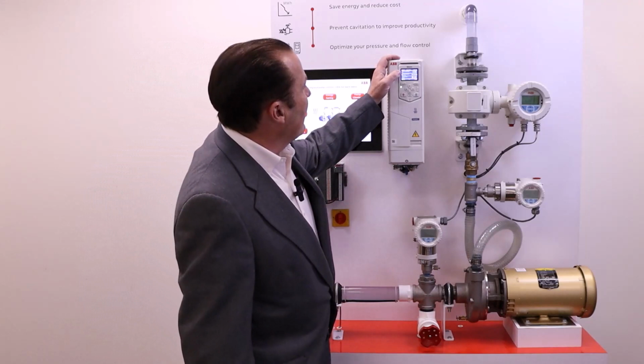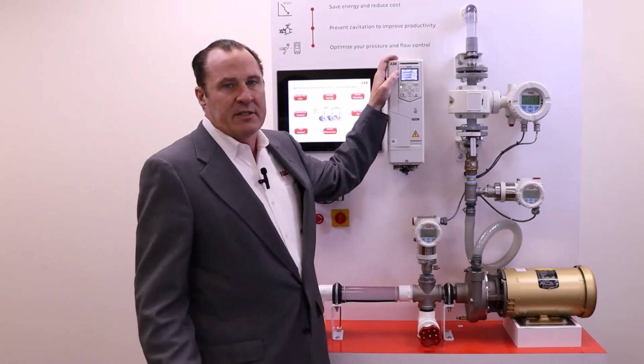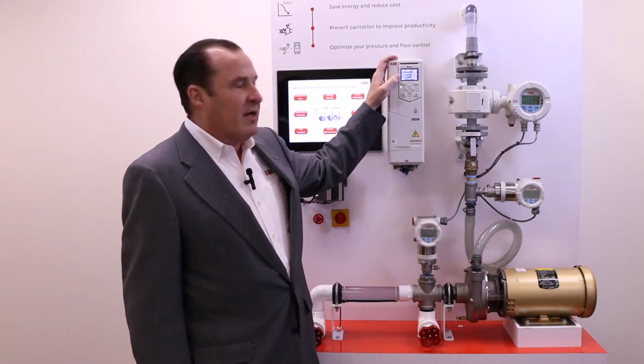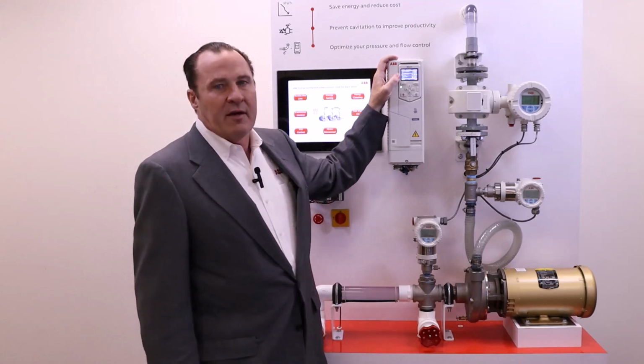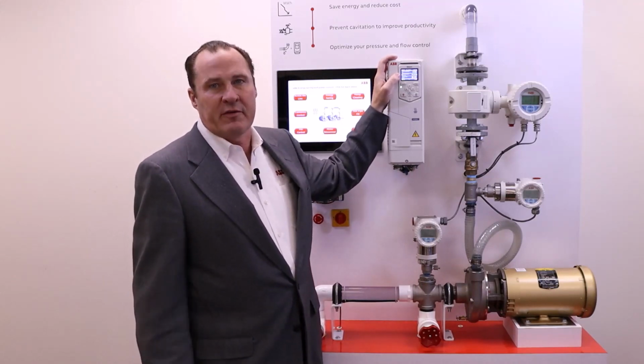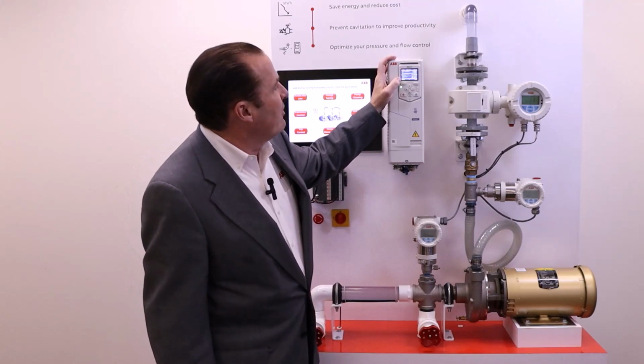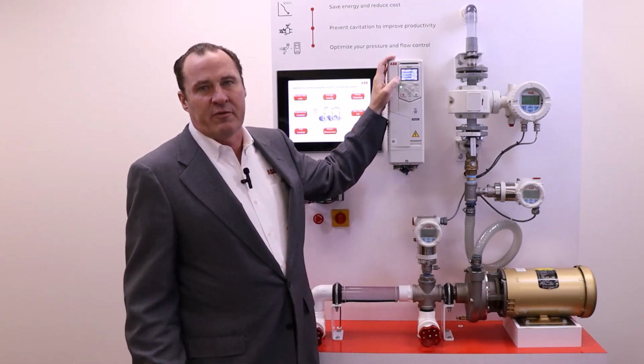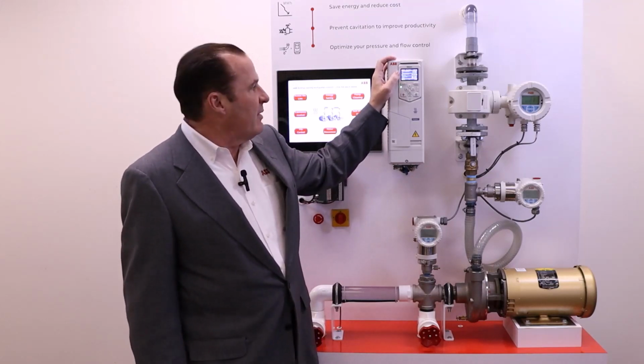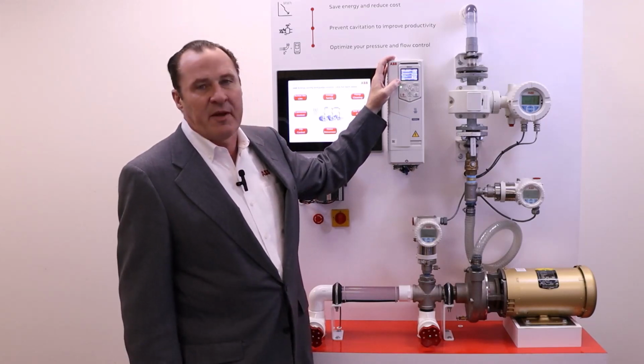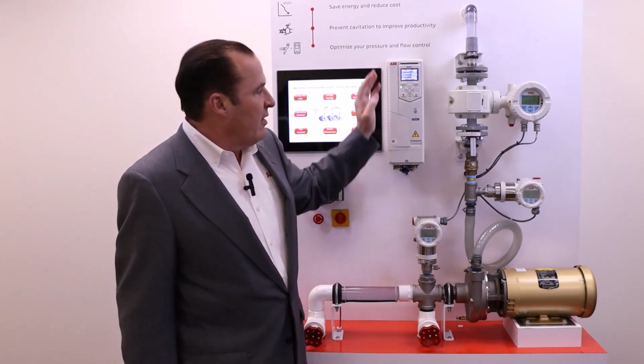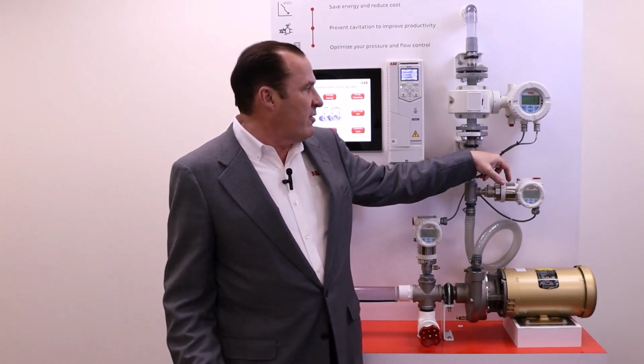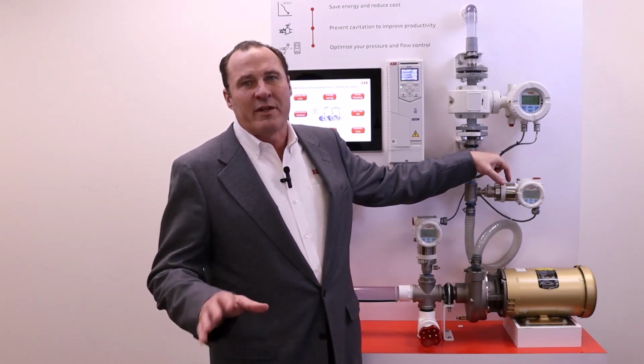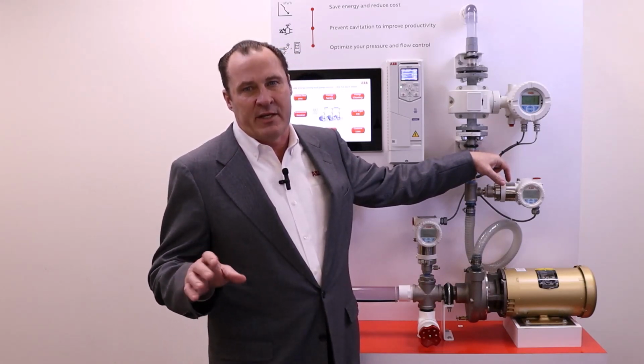I look at this right now, I see that my horsepower is at 0.56 horsepower. I see that my water column right now is 19.59. And I can see that my flow is 38.46. It's stabilized at those points, and this is my fully operational point. If I go all the way to the other side and stop the flow, that's my zero flow pressure, my zero flow right there. Okay, that's one data point.